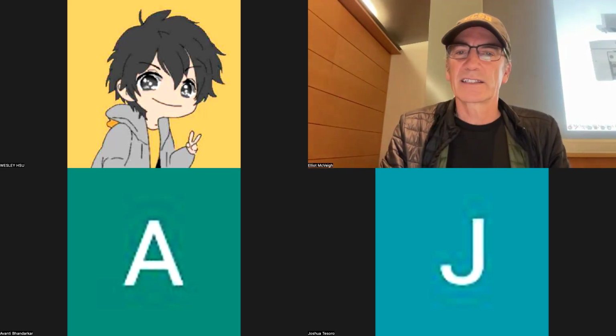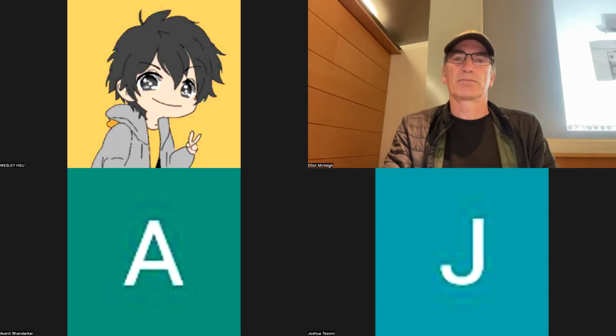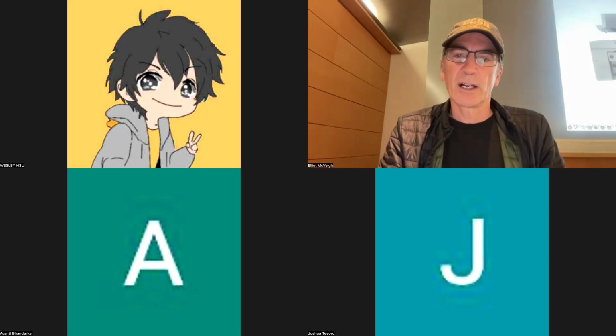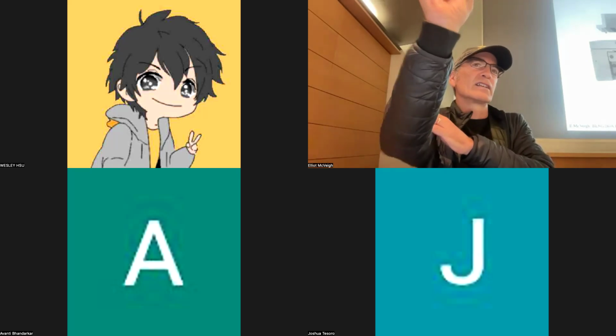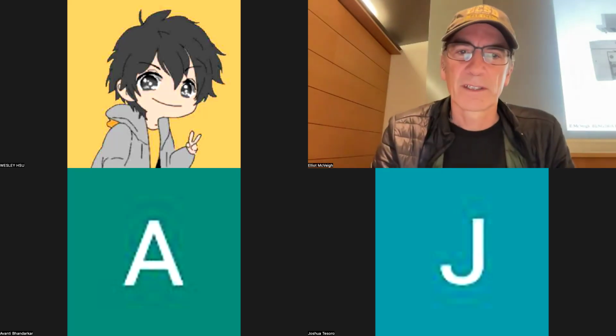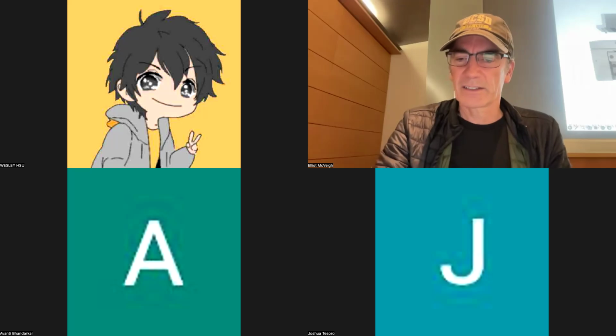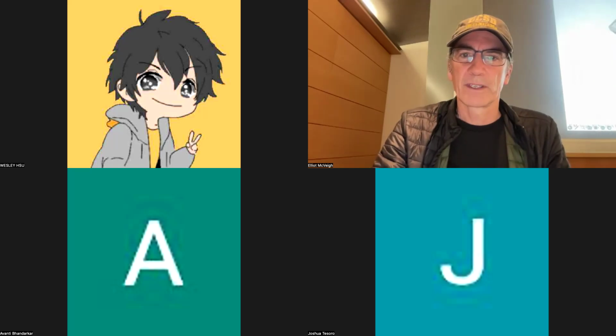But this is the anti-scatter grid. You can see it's pretty severe, right? If I look up from a single point on my detector up through the grid, I can only see a very select direction, right? And it goes back to the target, okay? And so that's what the mechanics of a normal detector look like.